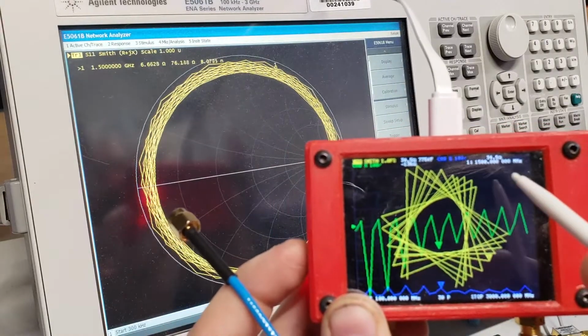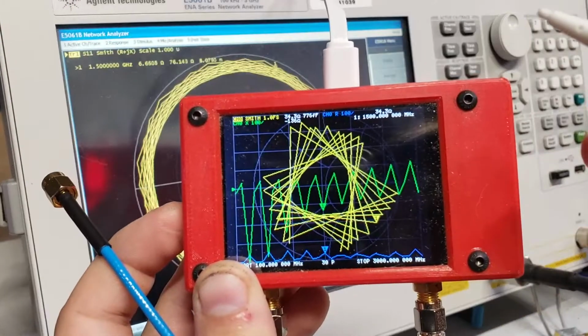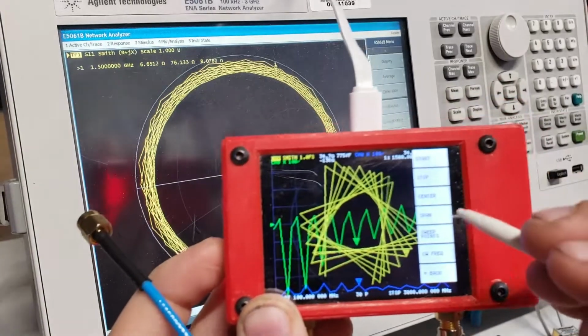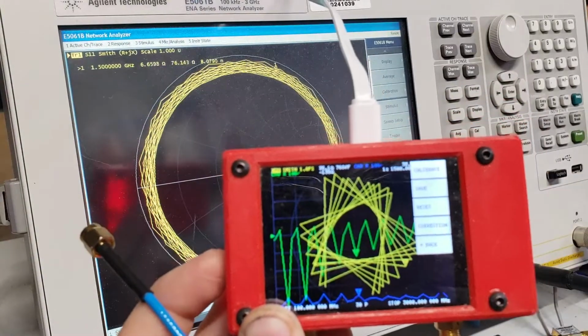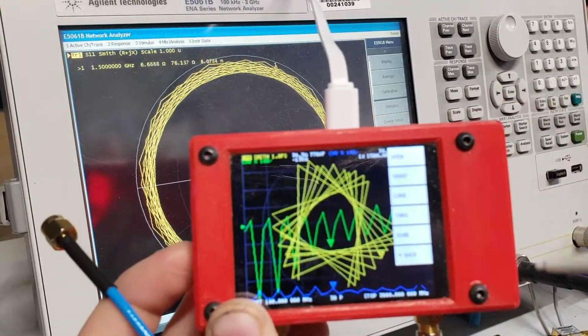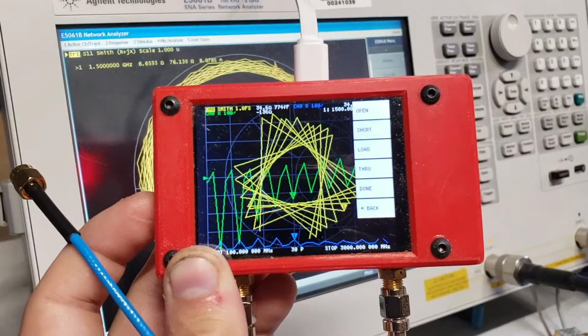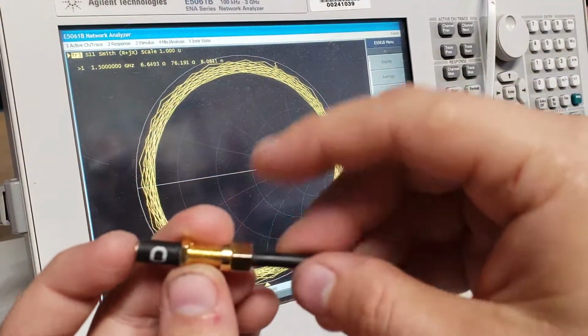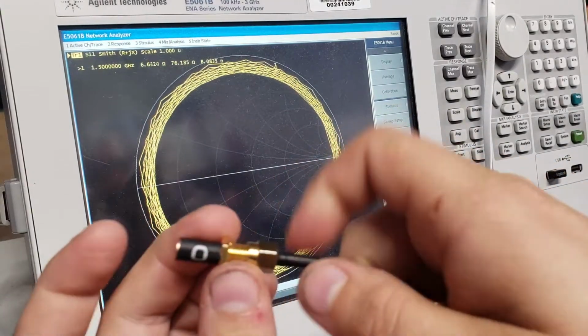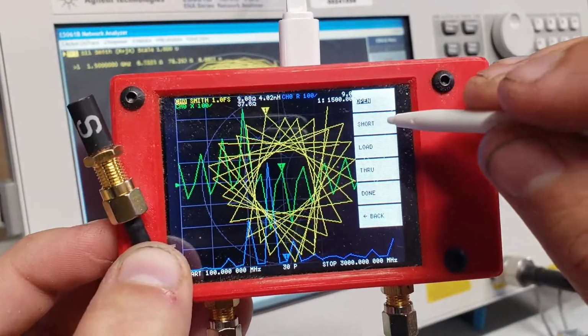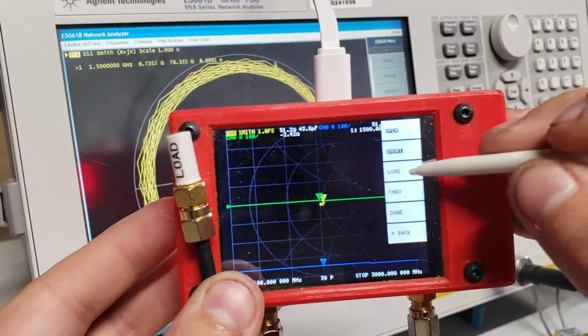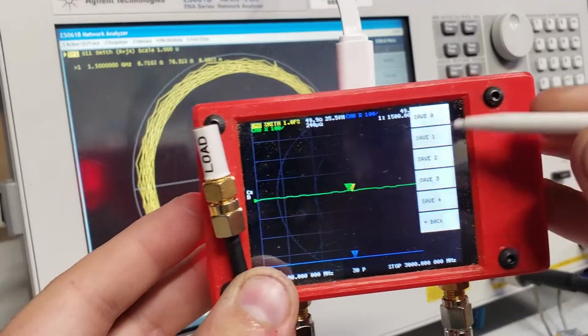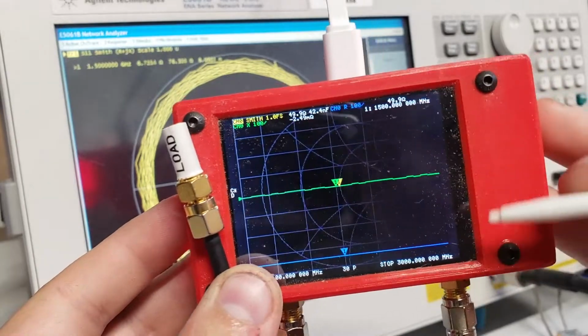And then I put a marker at 1.5 gigahertz, and I went ahead and did a calibration for the NanoVNA V2. Make sure when you put your standards on, I'll be using a female calibration kit in this case, you don't spin the female SMAs inside the male connector. Spin the outside of the male connector, press it in, don't let the cable spin, and good to go. So go ahead and do an open, short, and a load real quick here. Hit done, and then save that into calibration 0.